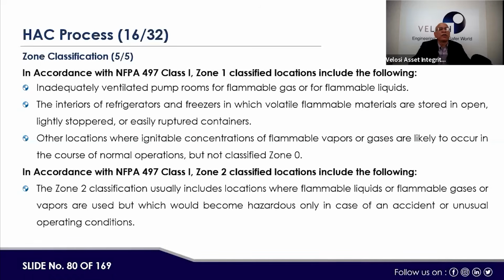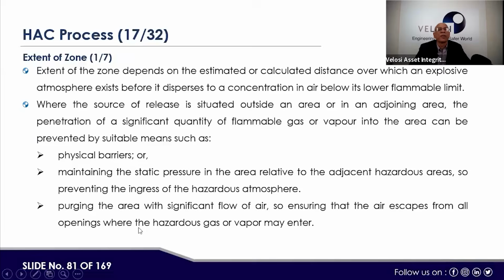Similarly, the definition in accordance with NFPA 497 Class 1 Zone 1 classified location includes the following; same continuation is there. Then, according to NFPA 497 Class 1 Zone 2. Zone 2 is important. Zone 2 classification usually includes locations where flammable liquids or flammable gases or vapors are used, but which would become hazardous only in case of an accident or unusual operating conditions. So now, what is the extent of the zones?